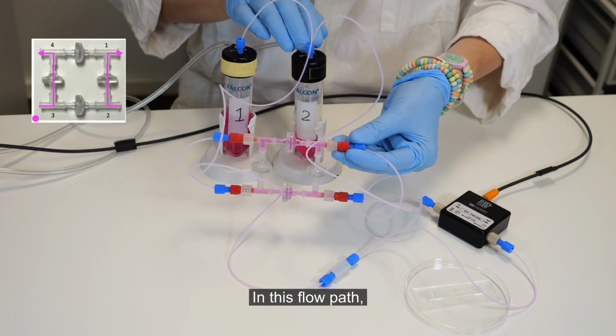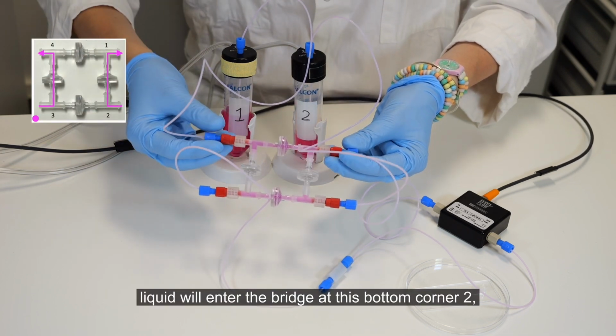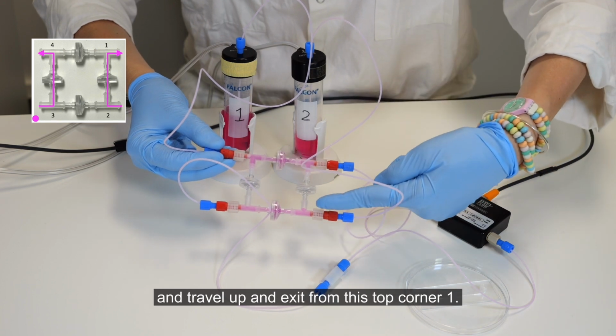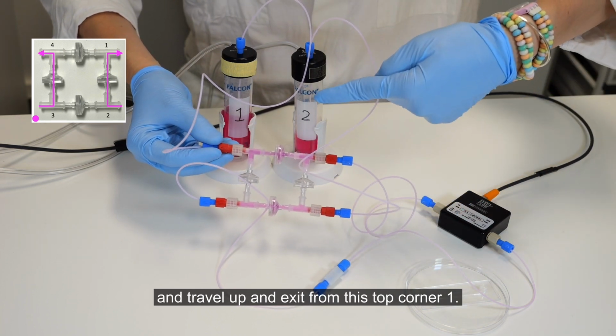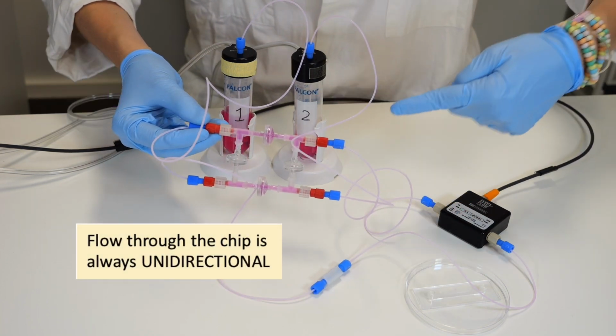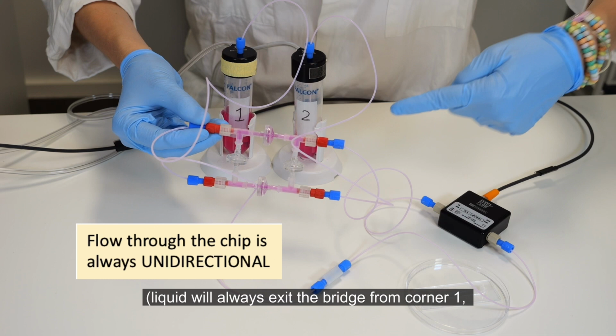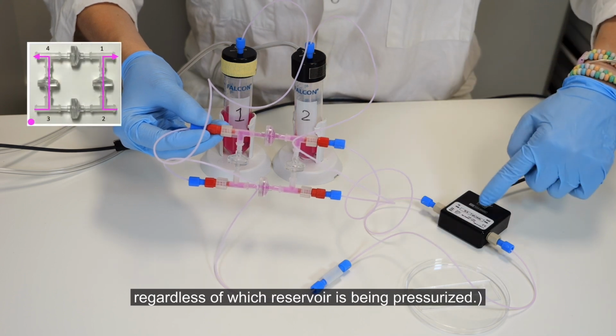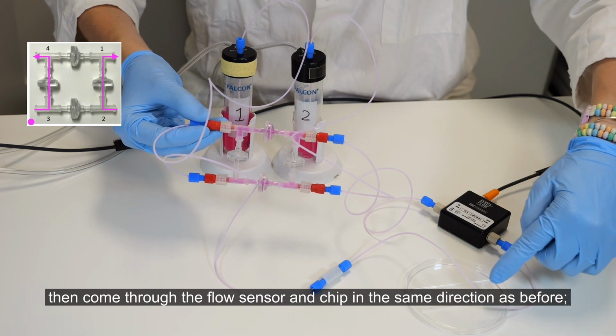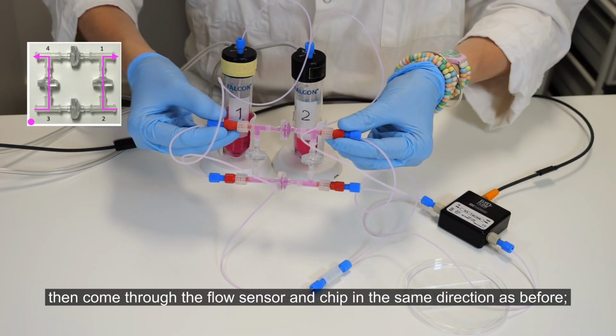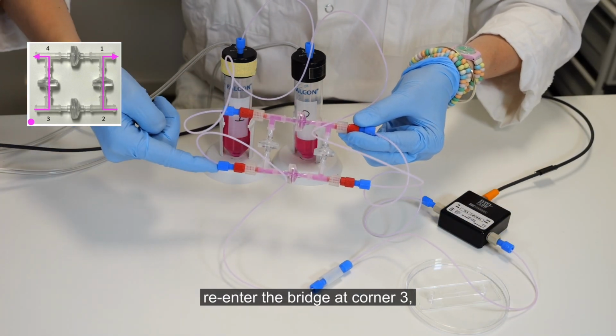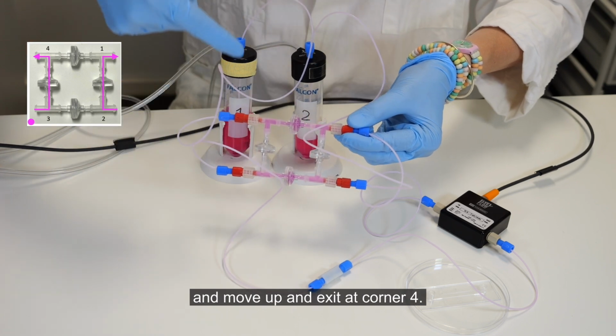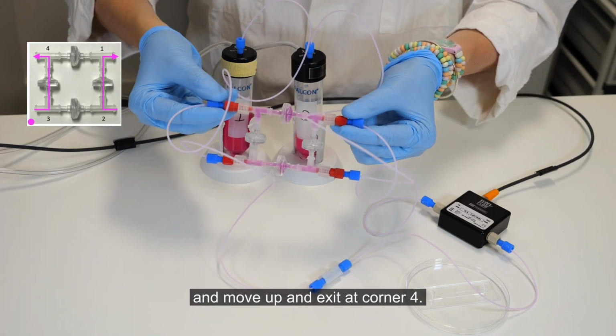In this flow path, liquid will enter the bridge at this bottom corner 2 and travel up and exit from this top corner 1. Liquid will always exit the bridge from corner 1, regardless of which reservoir is being pressurized, and then come through the flow sensor and chip in the same direction as before, re-enter the bridge at corner 3 and move up and exit at corner 4.